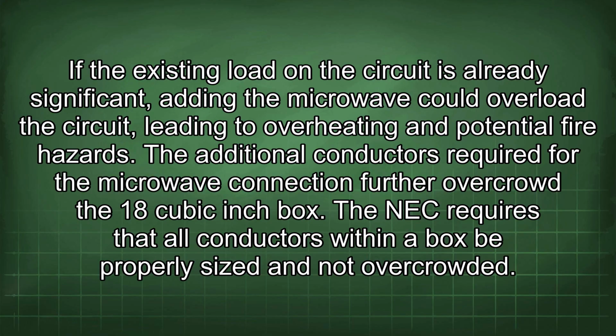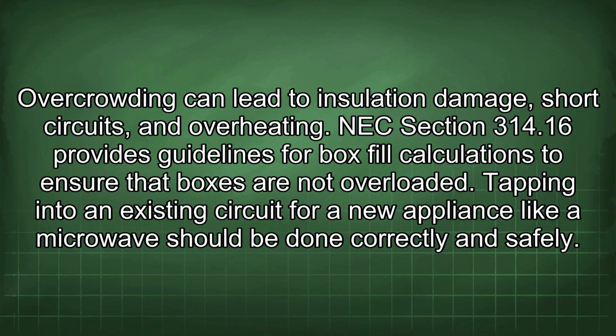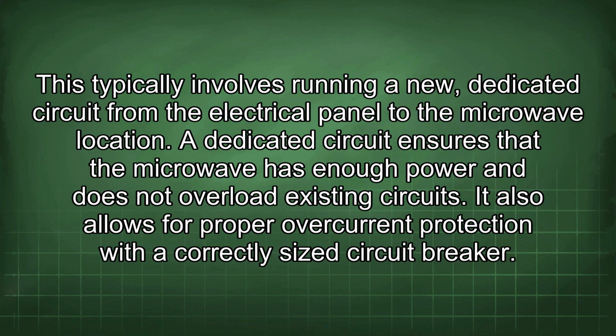The NEC requires that all conductors within a box be properly sized and not overcrowded. Overcrowding can lead to insulation damage, short circuits, and overheating. NEC section 314.16 provides guidelines for box fill calculations to ensure that boxes are not overloaded. Tapping into an existing circuit for a new appliance like a microwave should be done correctly and safely. This typically involves running a new, dedicated circuit from the electrical panel to the microwave location. A dedicated circuit ensures that the microwave has enough power and does not overload existing circuits. It also allows for proper overcurrent protection with a correctly sized circuit breaker.